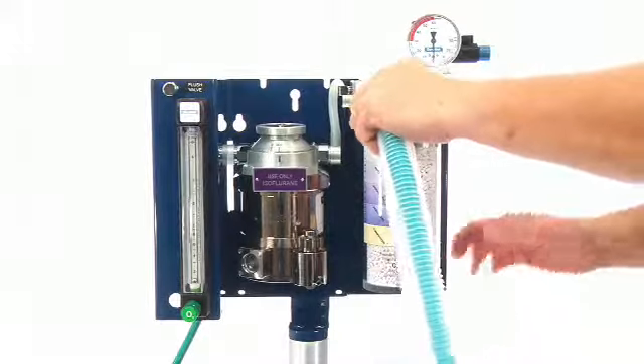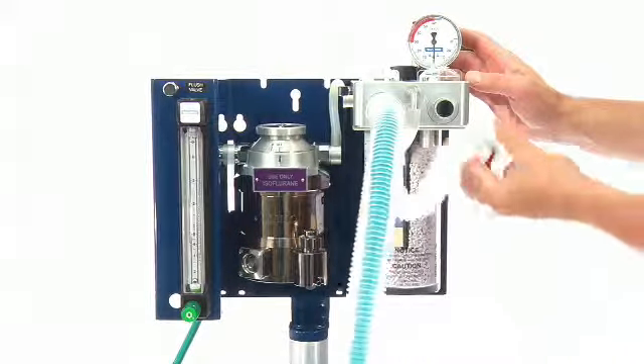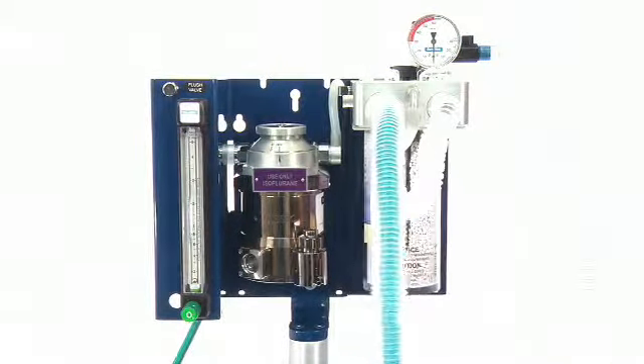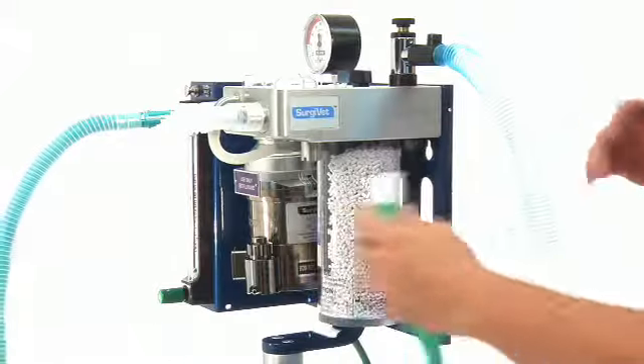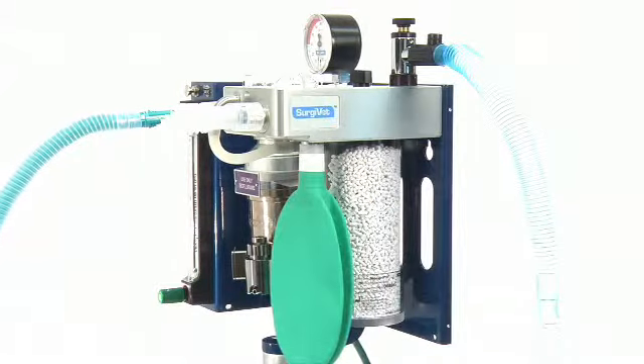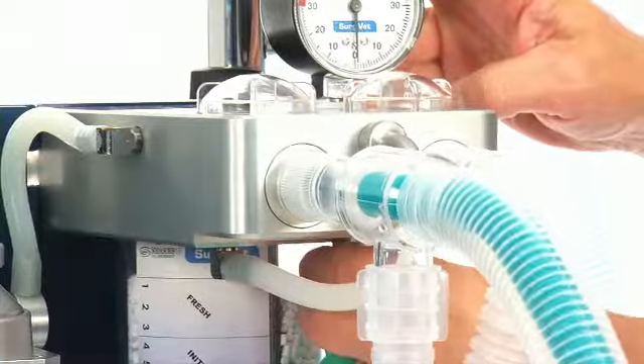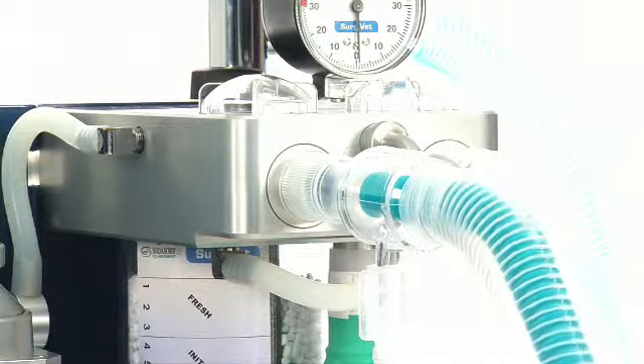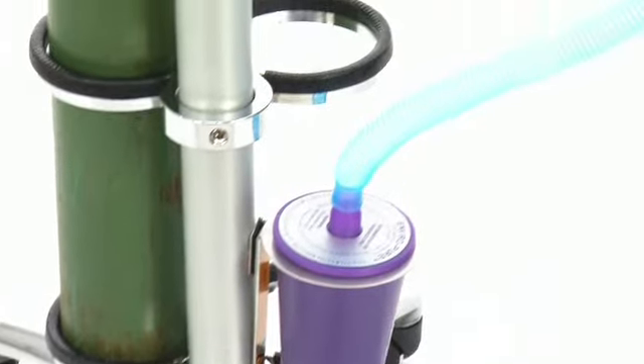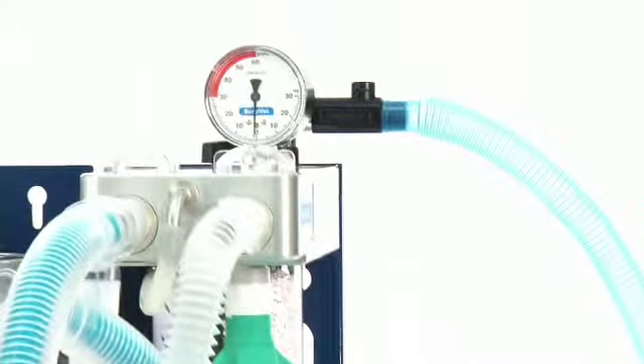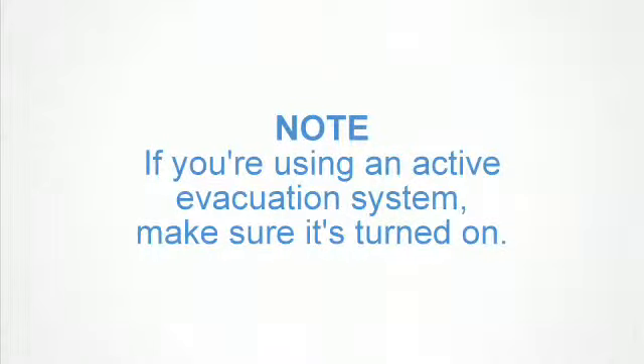Connect a rebreathing circuit, such as a Y or F circuit, to the inhalation-exhalation valves. Connect a rebreathing bag to the bag port of the machine and ensure proper configuration and secure connections. Check that the waste gas scavenging system is properly connected to the CDS 9000 machine. If you're using an active evacuation system, make sure it is turned on.